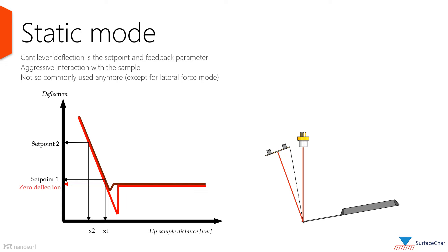In static mode, the cantilever deflection is used as the set point feedback parameter. Deflection, read by a laser reflecting from the cantilever onto a photodiode, is representative of the cantilever bending, which in turn is directly proportional to the force applied by the cantilever to the surface. The static mode results in a relatively aggressive interaction with the surface.